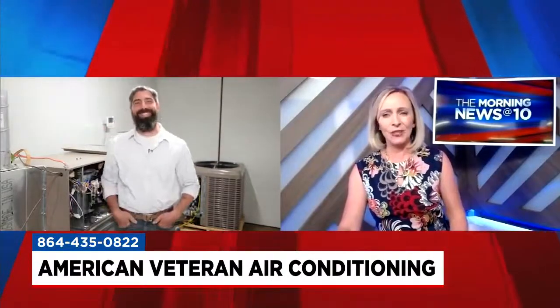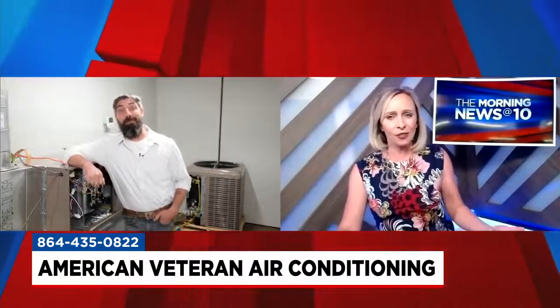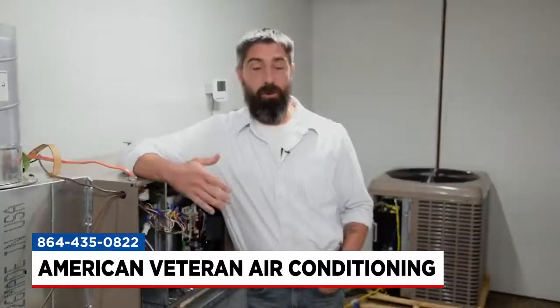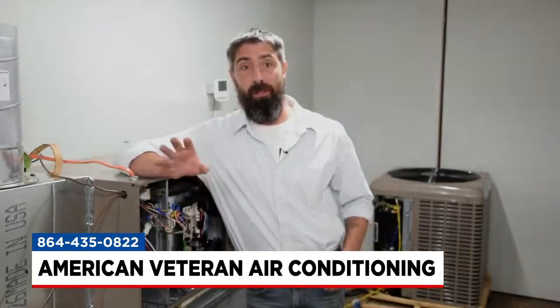Good morning. So first, we're talking about the American Veteran AC repair experience. For somebody needing a repair, what are some of the common replacements you're seeing? This time of year, especially when we hit that first big heat wave, usually capacitors. Fire ants are a big concern around this time of year. So if you want to prevent some repairs, get some fire ant killer around your unit. They will literally march through to death inside of your contactor and ruin your day.